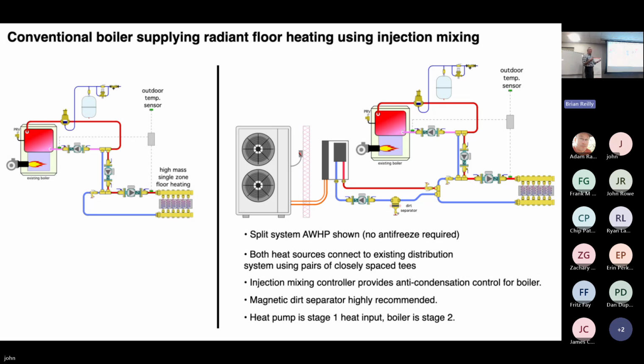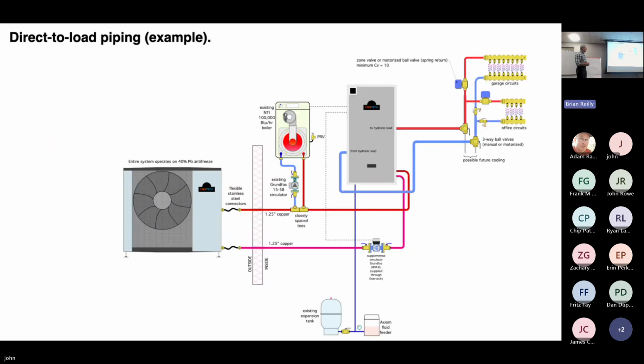And again, you could generate 100 different possibilities easily for what you might find in the field. I've tried to pick some that are somewhat common, and I've tried to apply what we talked about earlier with either parallel piping of the heat pump and the boiler or the closely spaced T's. Okay. Let's see, direct to load. This is basically an Enertech schematic there. This is the system without the buffer tank. This is a hydro split.